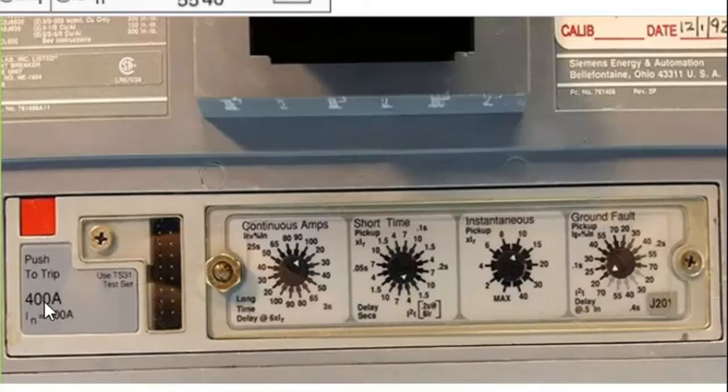current rating of the circuit breaker. So as you are adjusting this, it will give you a percentage of this. So if you take 20 as it is here now, or adjust it to 50, it means that you are using the breaker as a 200 amps breaker. Are we getting it? So this breaker has an added feature, which means that since it is microprocessor based, it helps to store events that are happening in the circuitry.